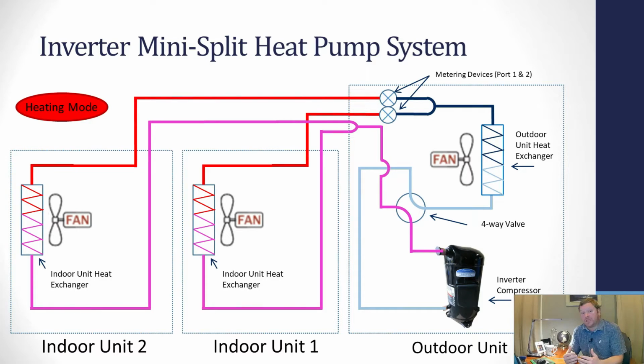Where you start to run into problems is as unit number 1 starts to get closer and closer to that target temperature. Remember, it has a lower target temperature of 73.5. The compressor is going to start to slow down, but still see the master bedroom with a bigger difference between its return air and target temperatures. So what the compressor can't do is slow down enough for the living room to not slightly overshoot. And so what generally happens is while the master is still calling, the compressor slows down as much as it can to allow the living room to not overshoot, but allow the master suite to still get to that target temperature. But it usually can't slow down enough, and the living room indoor unit 1 will start to slightly overshoot.